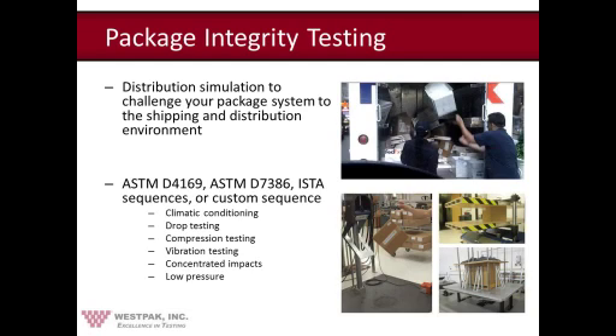A lot of clients will ask us what test sequence they should use for their product, for their packaging, which standard is best. For the purpose of medical device package validation testing, our recommendation would be sticking with what's on the FDA approved list. Right now, for package testing, the FDA recognizes ASTM D4169 and D7386. So we would recommend going with either of those test sequences for the time being.